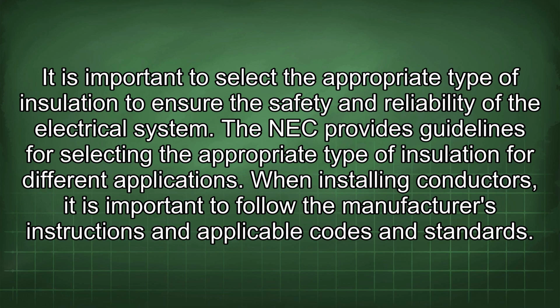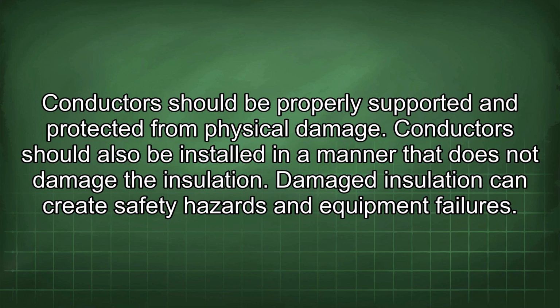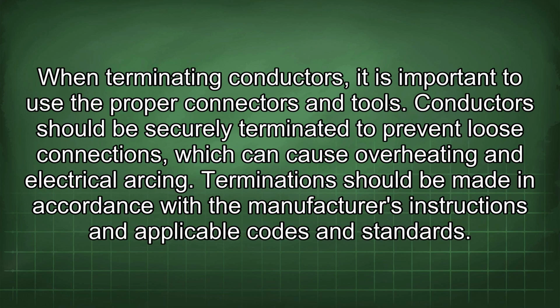When installing conductors, it is important to follow the manufacturer's instructions and applicable codes and standards. Conductors should be properly supported and protected from physical damage. Conductors should also be installed in a manner that does not damage the insulation. Damaged insulation can create safety hazards and equipment failures. When terminating conductors, it is important to use the proper connectors and tools. Conductors should be securely terminated to prevent loose connections, which can cause overheating and electrical arcing. Terminations should be made in accordance with the manufacturer's instructions and applicable codes and standards.